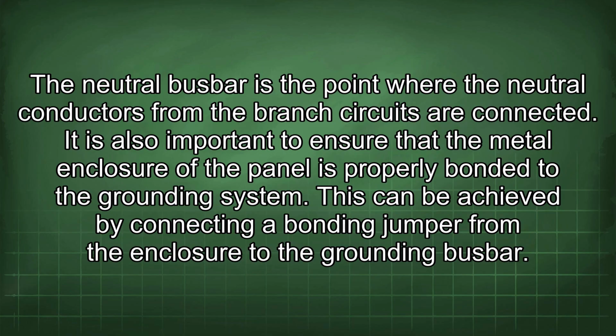The neutral busbar is the point where the neutral conductors from the branch circuits are connected. It is also important to ensure that the metal enclosure of the panel is properly bonded to the grounding system. This can be achieved by connecting a bonding jumper from the enclosure to the grounding busbar.